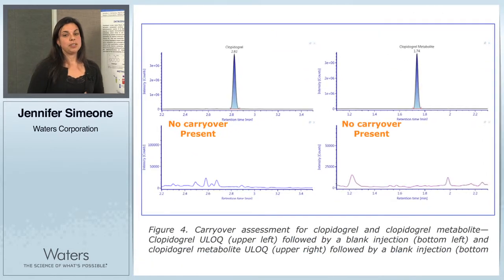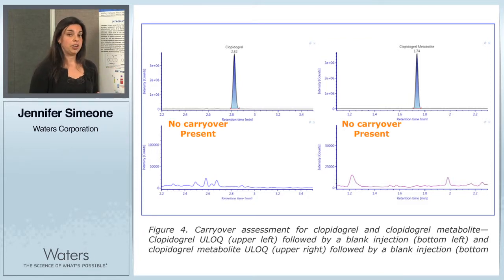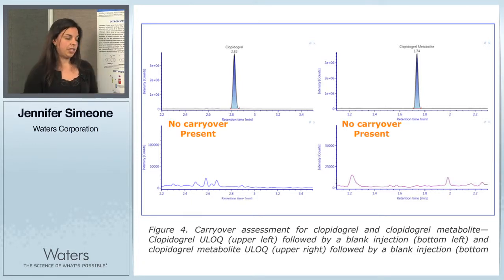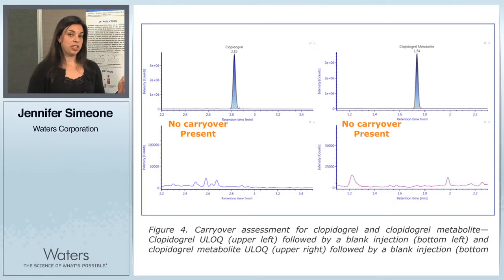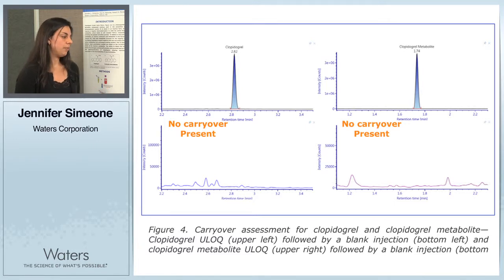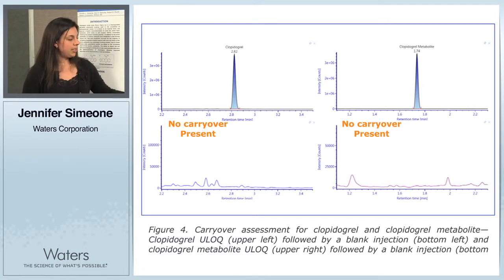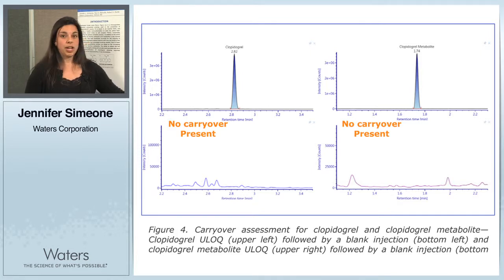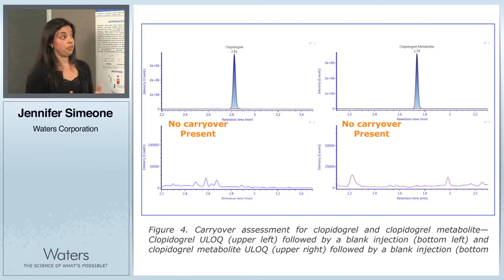Another important aspect of any bioanalytical method is to assess for carryover. If you have a high concentration sample, you don't want it carrying over into your next one because it'll give you incorrect results. The way you test for this is to inject your highest calibration standard, and then immediately following that inject a blank sample, which should have none of the analyte in it unless it's being carried over. In this figure, you can see that for both Clopidogrel and its metabolite, the blank injection following the highest standard is clean — so this assay shows no carryover.